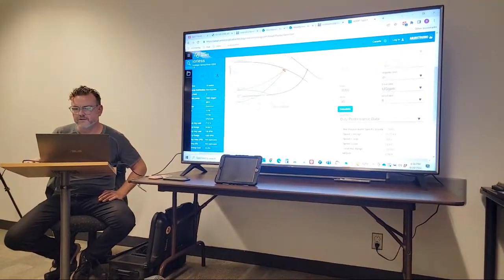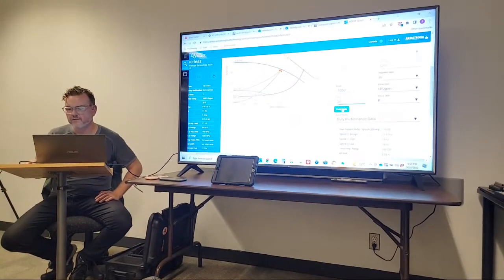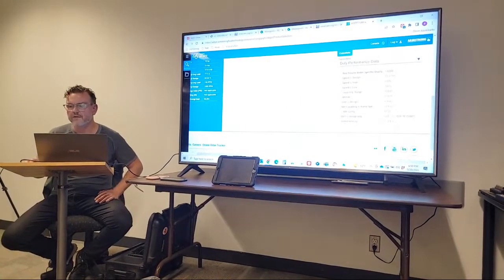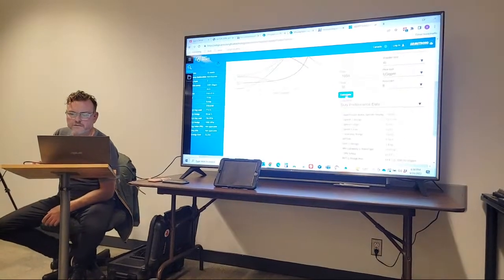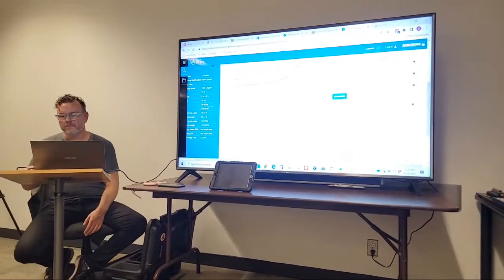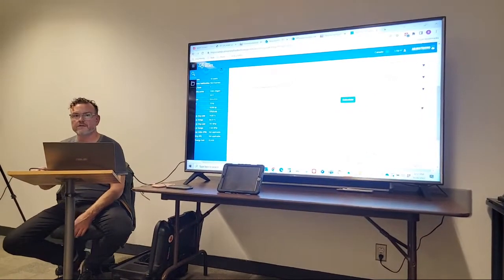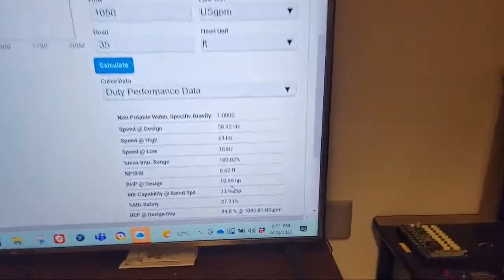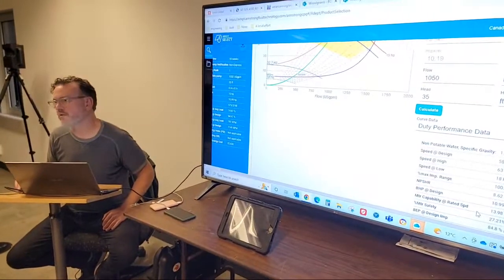Exactly. So now I'm just going to go over here and say, whoop, somebody throttled that valve. That was 9.4, right? Let's see what that does. Horsepower, right? So now you can start to see just slight changes onto electrical, right? So there you go. So just some things that you sort of want to look for.